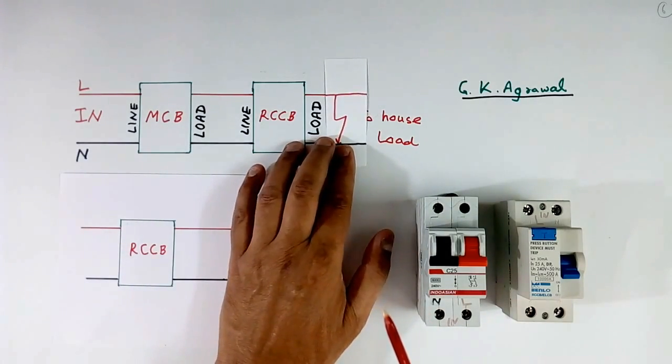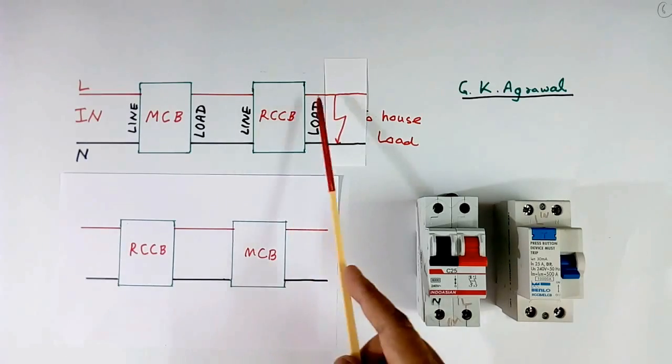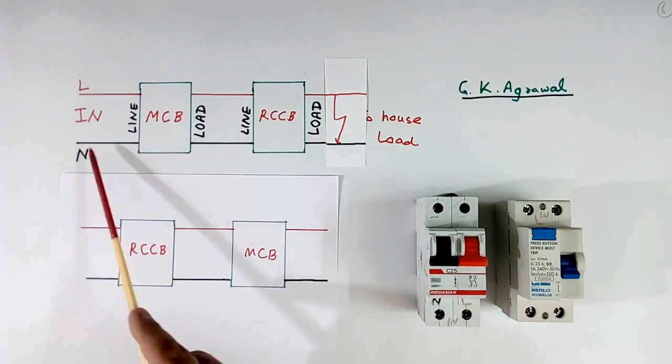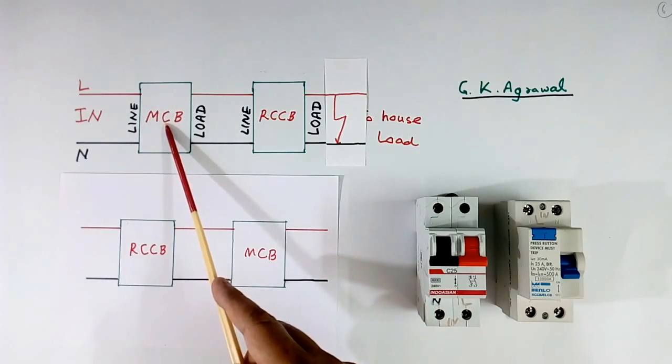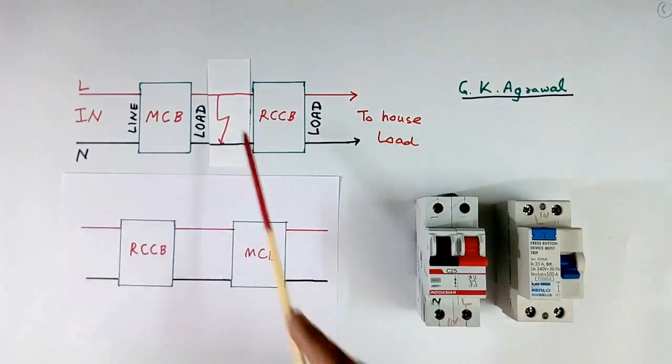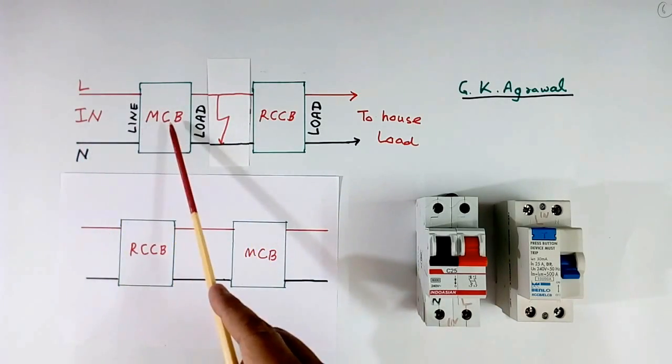Suppose there is a fault here. When fault happens between line and neutral, then this current will flow like this. So this fault current will flow in MCB and it will protect us. It will trip. If short circuit happens here, then also fault current will flow like this and MCB will trip.